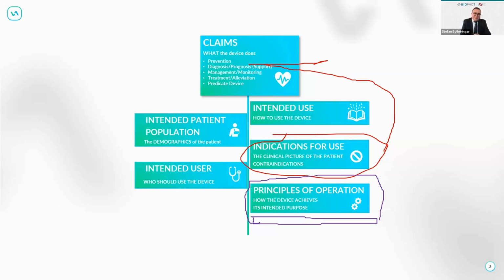Looking into software as a medical device which is not AI-based, but uses a general algorithm, you can simply place that algorithm as your principles of operation. So it shows you exactly the flow, what it does.